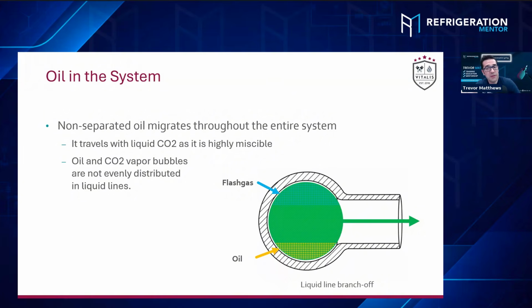I had someone call me up last night to ask me this question: why is some manufacturer doing installs, why does some come off the side, why does some come off the bottom? The two biggest things for you is the flash gas for maybe the last 2 systems. So basically, if you're doing it off the bottom, you believe that as it goes down, the last couple may get a bit more of that flash gas, correct? Yes. And then also when you come off the bottom, the saturated oil is heavier, or is with the oil, and it's traveling down into the evaporators a bit more. It's not a trap, but it's a place where it won't feed into the evaporators. Because a lot of times our liquids are overhead. Like we're in a big store, we're running them overhead and then we're dropping them down.